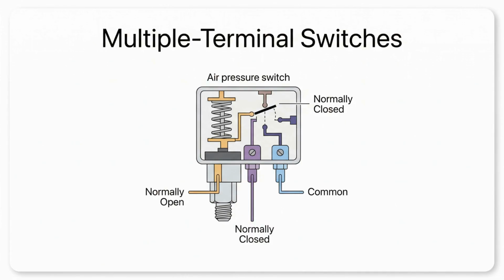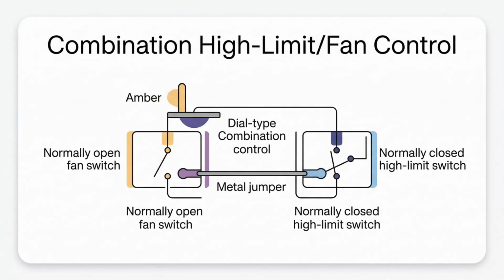Another common multi-terminal device is the combination high limit and fan control. It houses a normally open switch to turn on the blower when the furnace heats up, and a normally closed limit switch that cuts power to the gas valve if the furnace overheats. A small metal jumper often connects the two, so they can share a single power source.